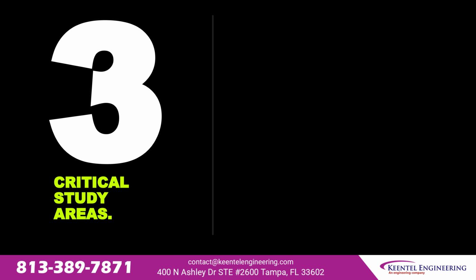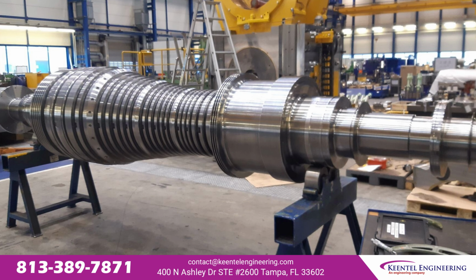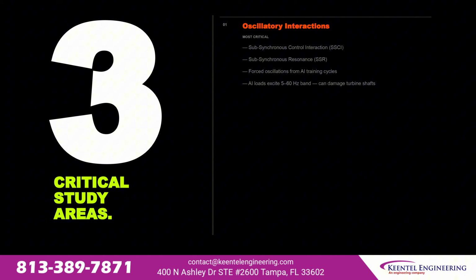3 study areas are critical for any large AI load interconnection. First, oscillatory interactions, the most critical. Sub-synchronous control interaction, sub-synchronous resonance, and forced oscillations from AI training cycles. AI loads excite the 5 to 60 Hz band. That range can damage turbine shafts in nearby generators.